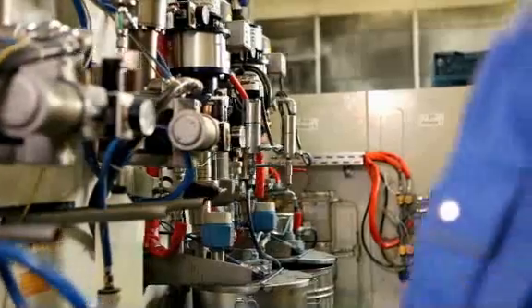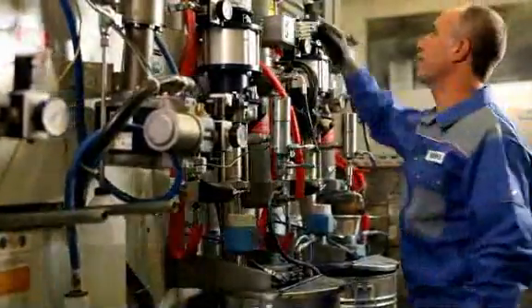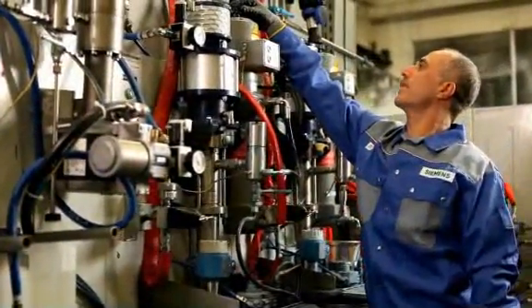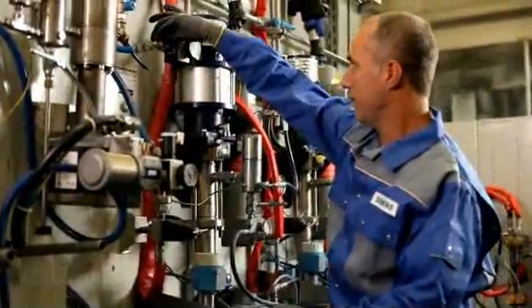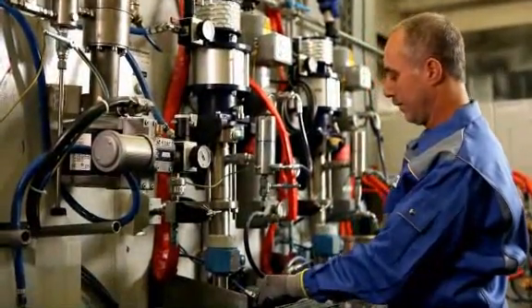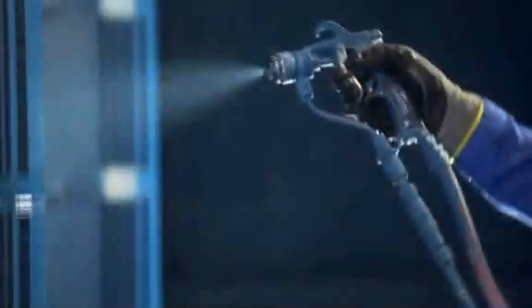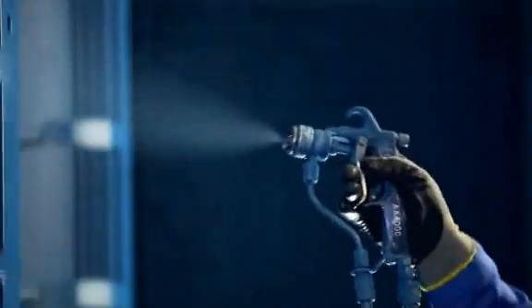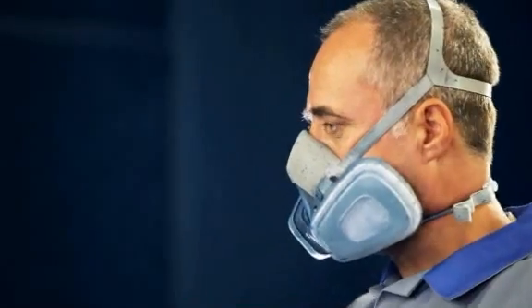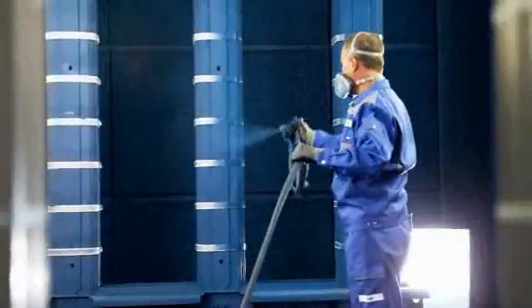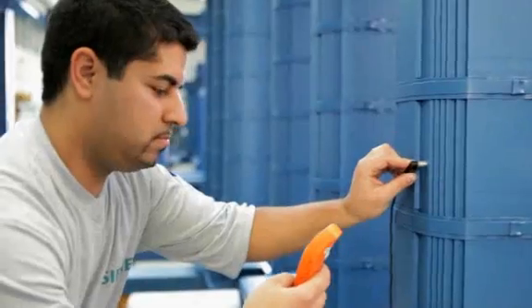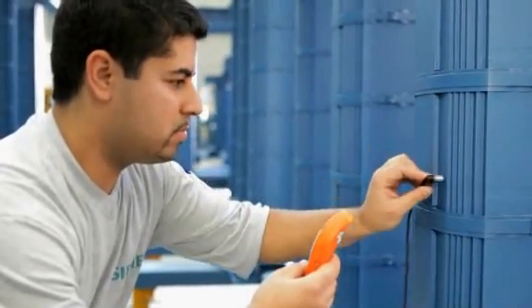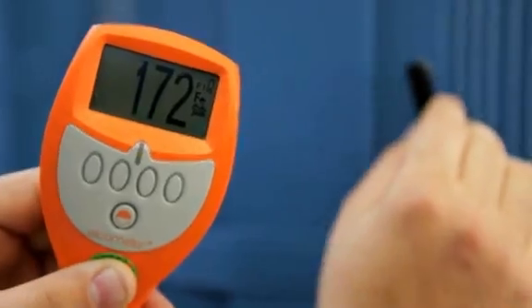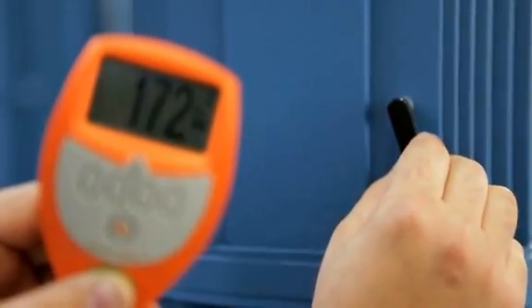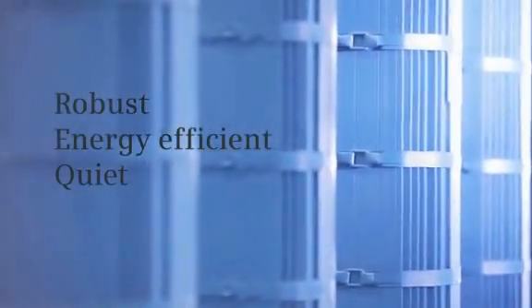The same applies to the painting equipment. It has to be eco-friendly and economical, of course, because efficiency is as important to us as quality. And as a Geafol is supposed to last for decades, every single core is carefully varnished in order to prevent corrosion. Exact measurement is one of our hobbies. The core is only approved for assembly if the thickness of its layers is correct down to the last micrometer.